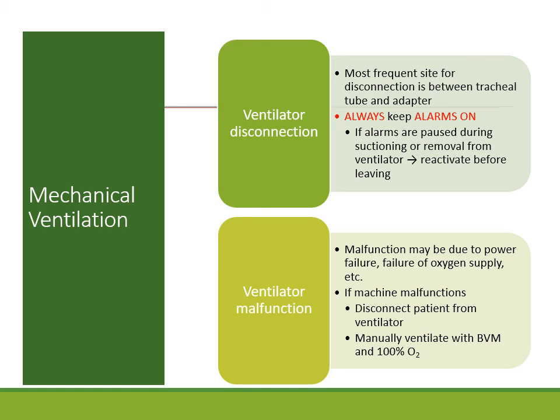The goal is to avoid mechanical ventilators becoming disconnected or malfunctioning. When turned on and operative, alarms alert you to problems. Most deaths from accidental ventilator disconnection occur when the alarm is off. Most accidental disconnections in critical care settings are discovered by low pressure alarms. The most frequent site for disconnection is between the tracheal tube and the ventilator tubing, so twist to secure more tightly.